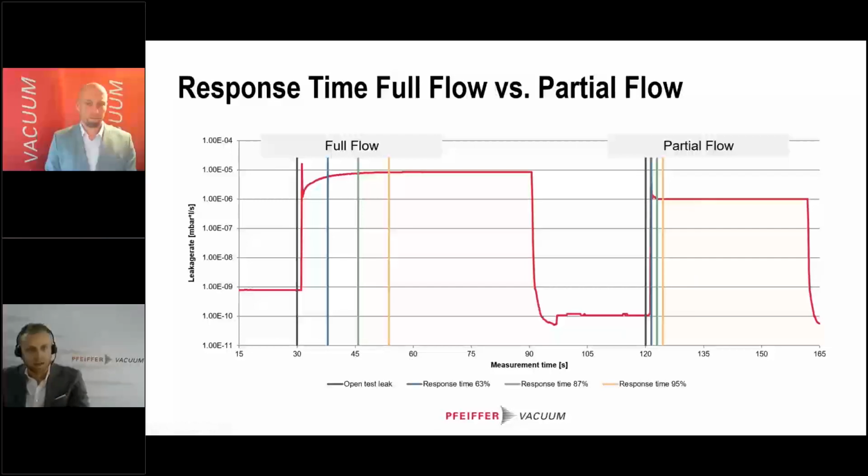The advantage that you have in the partial flow, however, is the response time. So you see here these vertical lines are the response times, and we see that those are much quicker for the partial flow in comparison to the left side for the full flow. Yeah, so this is basically a good summary of the pros and cons of the different methods.